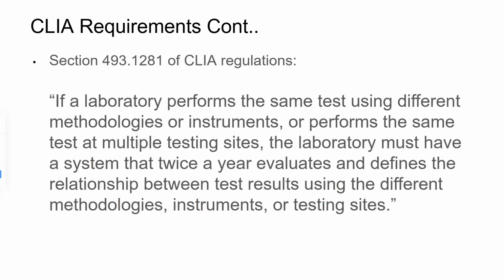If a laboratory performs the same test using different methodologies or instruments, or performs the same test at multiple testing sites, the laboratory must have a system that twice a year evaluates and defines the relationship between the test results using the different methodologies, instruments, or testing sites.